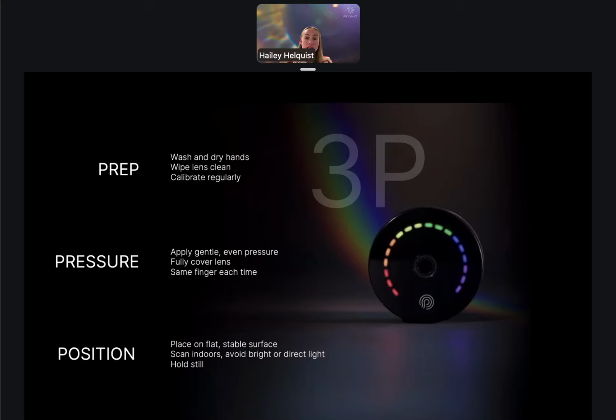The other thing as well is make sure that you're scanning indoors. Again, we are measuring light, the absorption of light into the skin. And so if you're in a really bright room, or if you're outside, we do a lot to help prevent excess environmental light leak into the device. But when you're out there in full sun, right, or it's really bright, that can leak through even your own finger and impact your score. And so best practice is to scan indoors if possible. If you are outside, find a shaded spot. Just make sure it's not out in full sun. This will also help with consistent scoring as well.